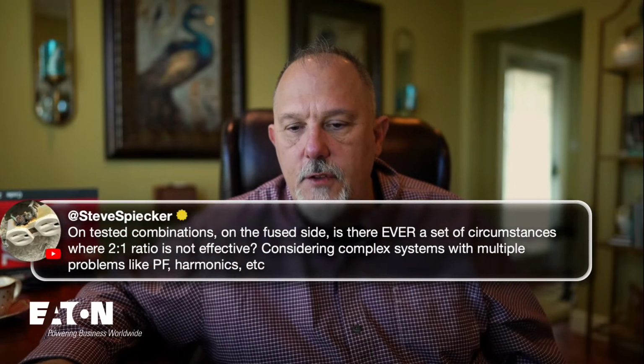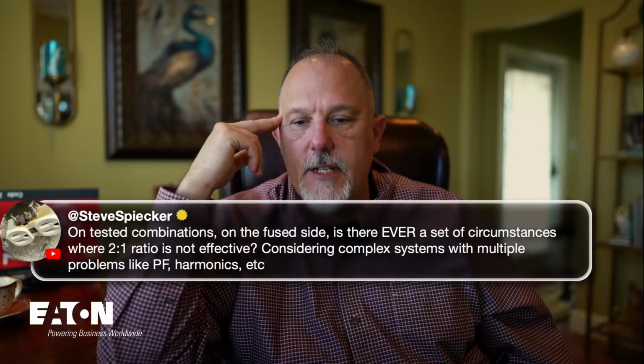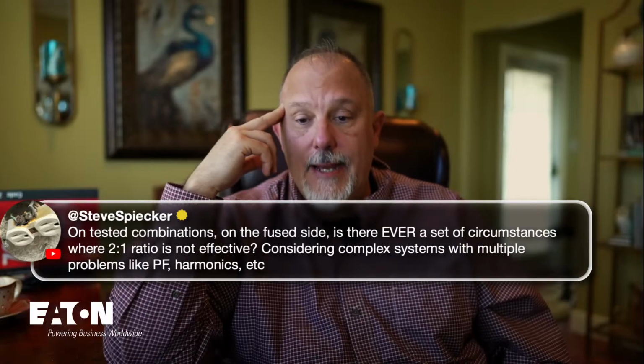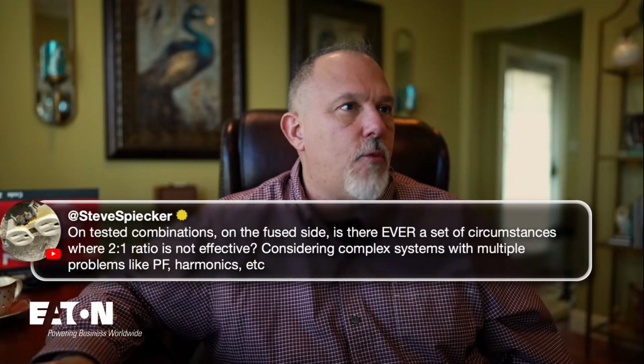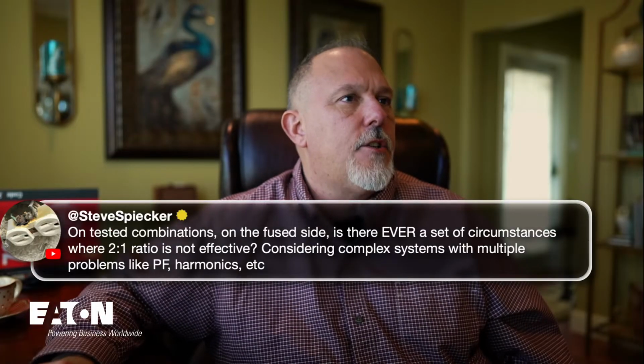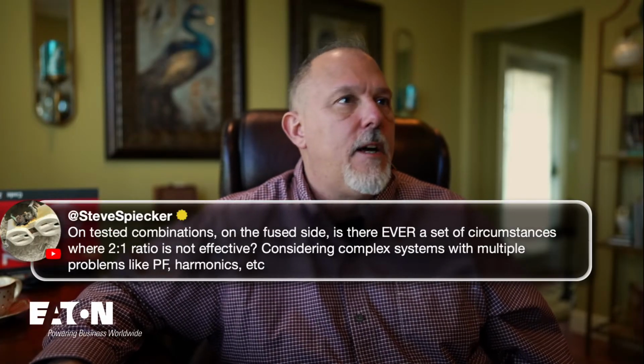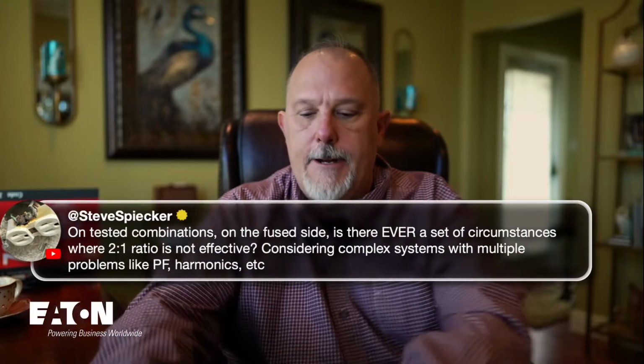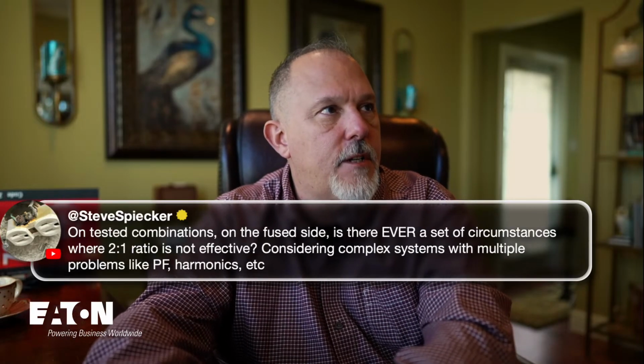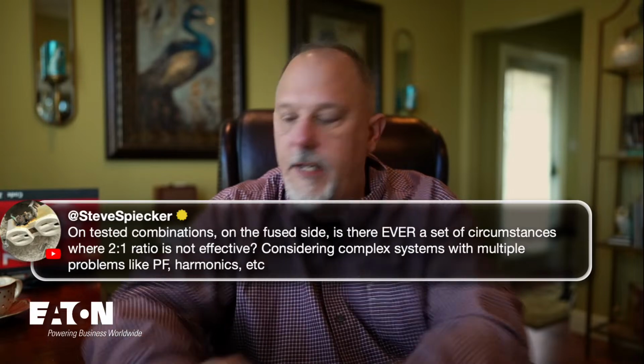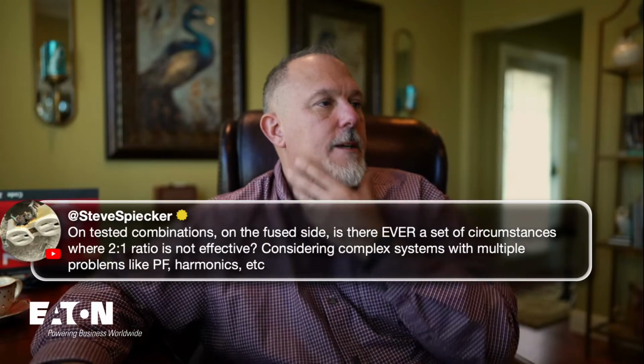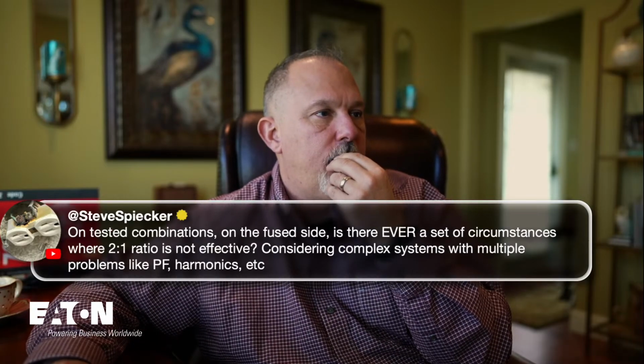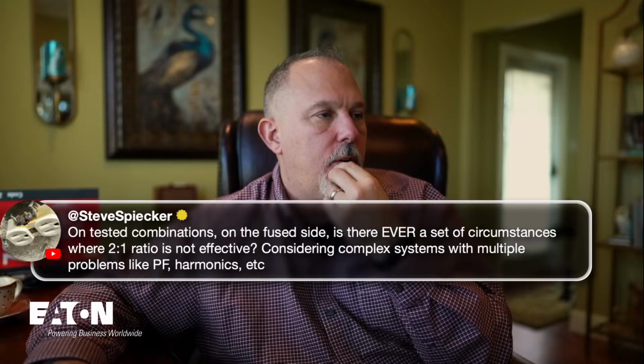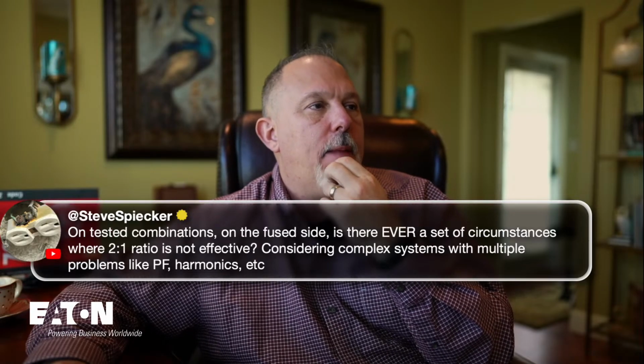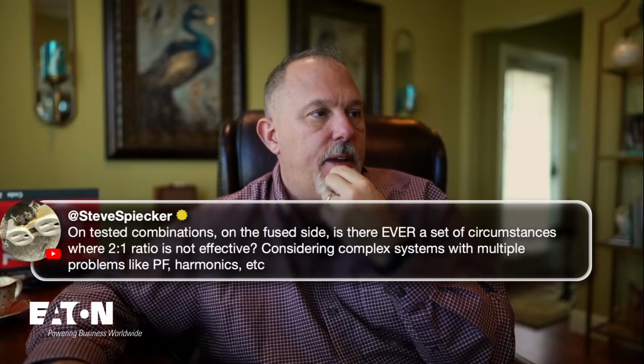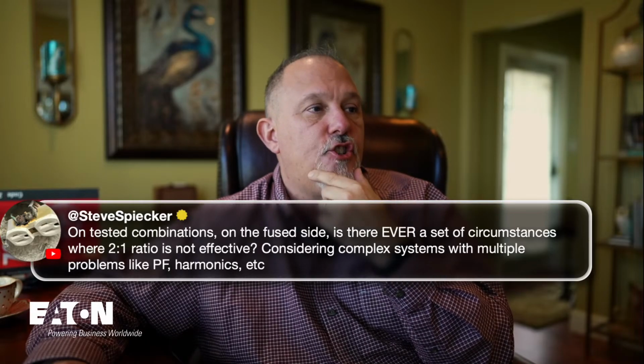On tested combinations on the fuse side, is there ever a set of circumstances where a 2-to-1 ratio is not effective? Yes. Good question, Steve. On the fuse side, a lot of people will say, selective coordination, I'm just going to go Eaton, because we have Bussmann, and we have tables. So a lot of people automatically think that if I have fuses, it's 2-to-1. Not true.